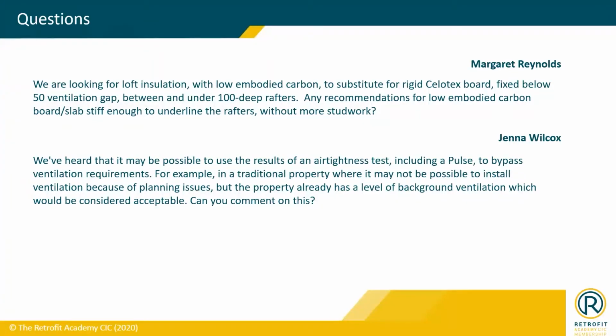Sure. Well, doing insulation will do some of the airtightness work for you, and replacing the windows will do a lot of the airtightness work for you. My experience is that what's challenging is putting in the background ventilation that you also need, especially if the windows don't have it. If you change the windows, it's not a problem. If you're not changing the windows, or the windows have been recently changed and don't have background ventilators, that's challenging. And my recourse would normally be to use wall vents rather than window vents.